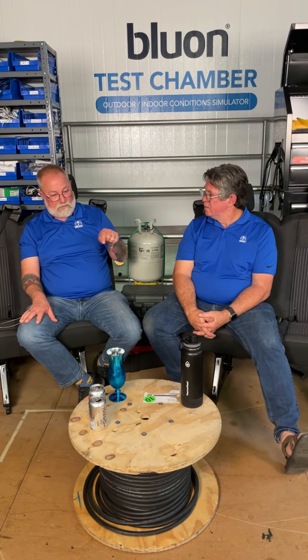They want to see the decimal point. So it's 62.8 pound suction on R22. They'll want to see that. They'll want to see the temperatures in the decimal points. So the whole world is switching over to digital. Does analog work? Yeah. Analog still works, except when you're getting into the new blends. The manufacturers, there's just not enough room on an analog gauge to put all the ribbons going around. Well, then what are you going to do on the dual column? Well, you know, you have the blue side and the red side, Mike. Yeah, but what if you got the blue side on a liquid? Then you're going to run into some problems.